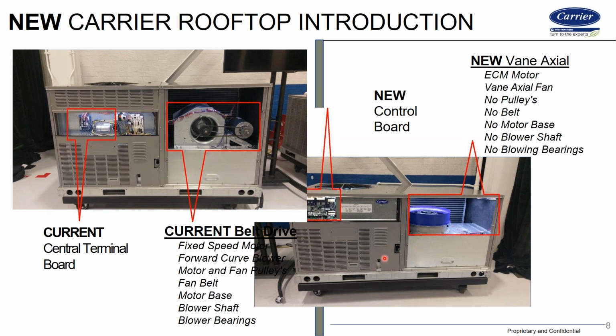So if you've got short cycling of supply to return air, that can heat up our return air above the maximum 85 degree return air temperature. And needless to say, if we're returning say 100 or 110 degrees at the ceiling, and we have our normal 40 to 60 degree temperature rise, we're over that main limit and it trips. So watch for recirculation of supply air into returns. If you can, get a two-way diffuser instead of a four-way, or whatever you have to do, and if you could possibly move the returns away from the supplies.